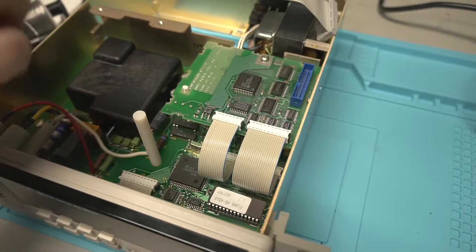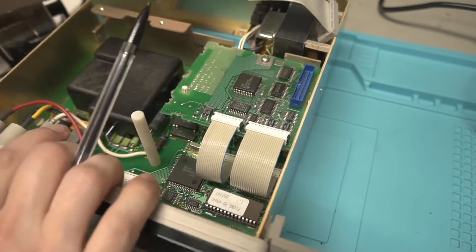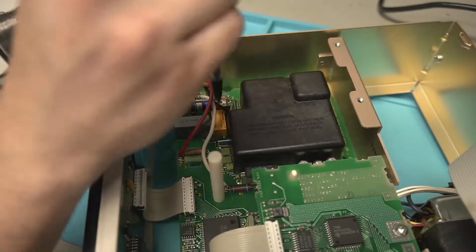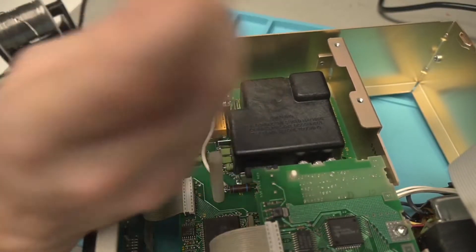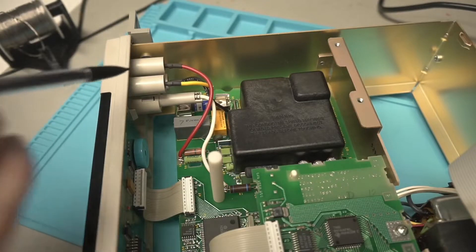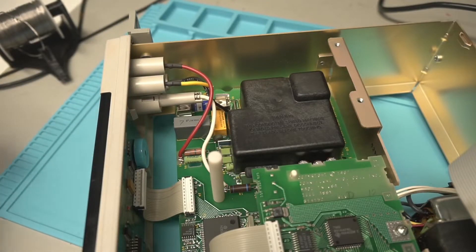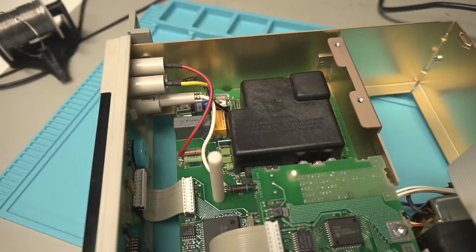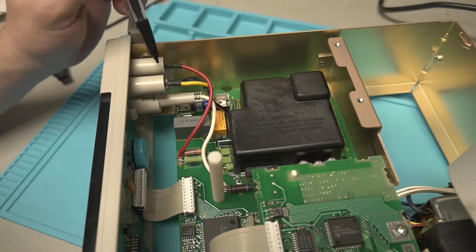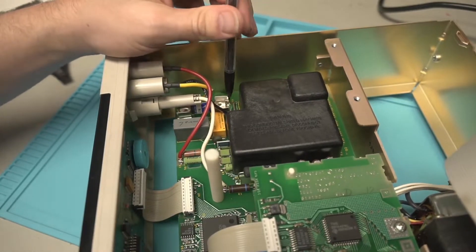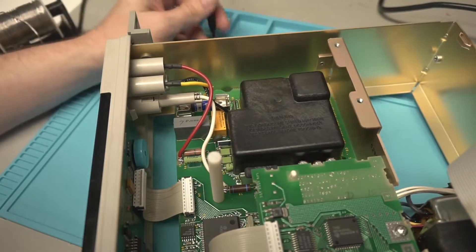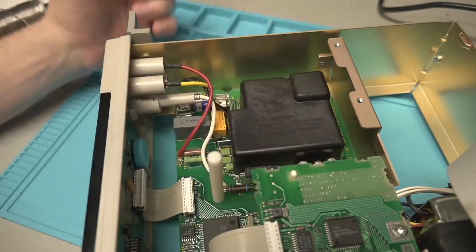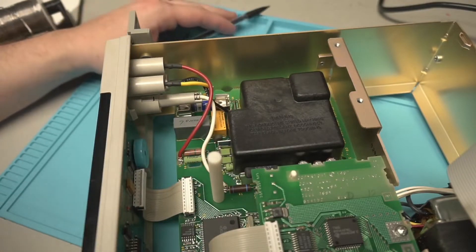We have a big fuse over here for the 10 amp and the 100 milliamp, the fuse is actually in here. You can open it up to get it out and take the fuse out of that holder there. So the fuse kit is changeable from the exterior while if you blow the 10 amp, you are going to have to open it up to get that out. And so that's really all I want to cover on the interior of this thing and just wanted to give you a quick glance.